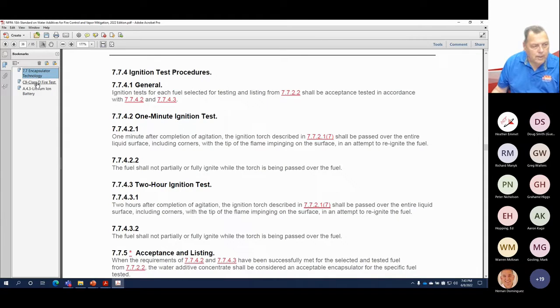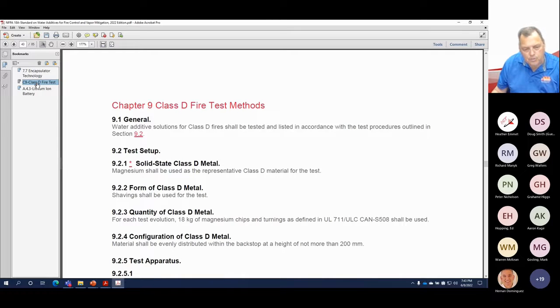When I show you the orientation of our molecules on the surface of the droplet, that's a big change in the fire protection world. You'd never put plain water on a Class D fire, because it breaks H2O into hydrogen and oxygen, both flammable explosive gases, causing fireworks. But we've changed the substance on the surface—we have an F500 molecule there. So because of this technology, there's now a need to conduct a Class D test.